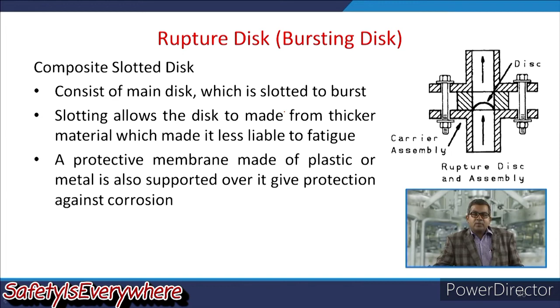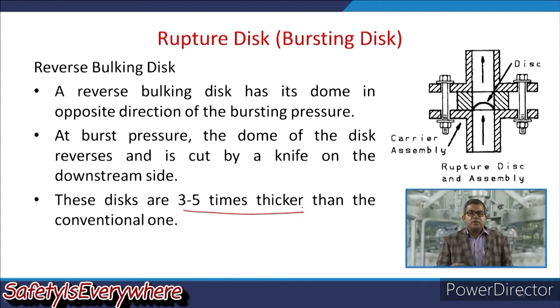Now we have a reverse buckling disc. A reverse buckling disc has its dome in the opposite direction of the bursting pressure. At burst pressure, the dome of the disc reverses and is cut by a knife on the downstream side. These discs are 3-5 times thicker than the conventional one, which we have discussed earlier.